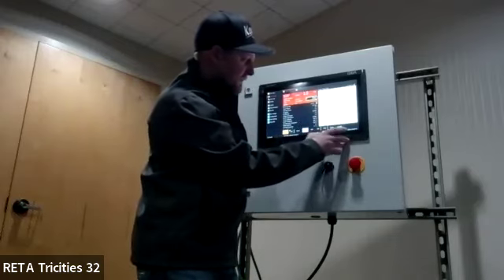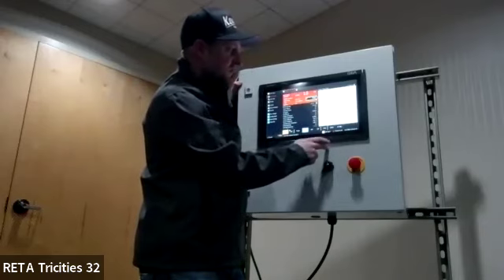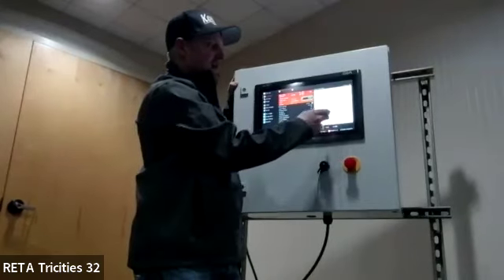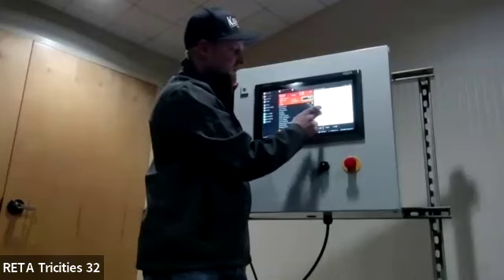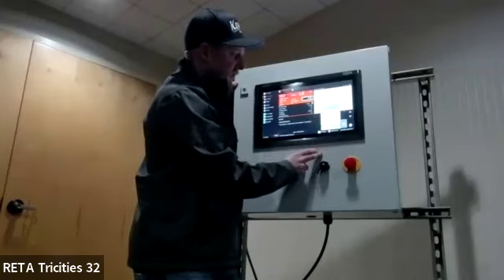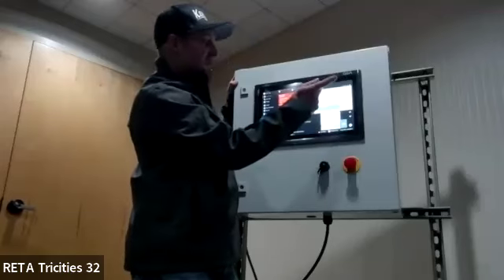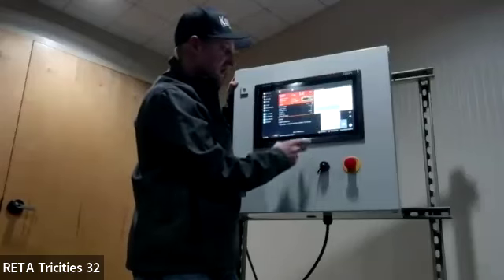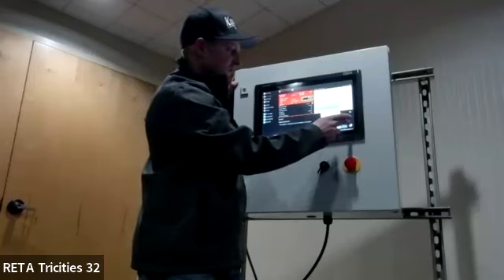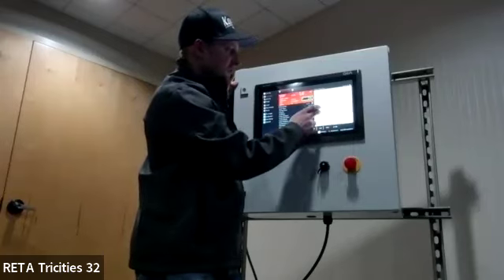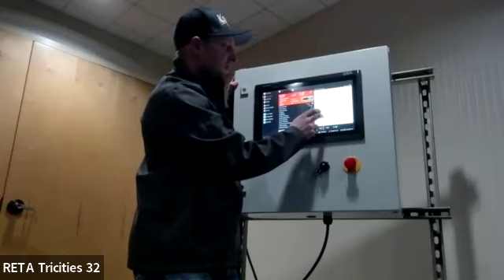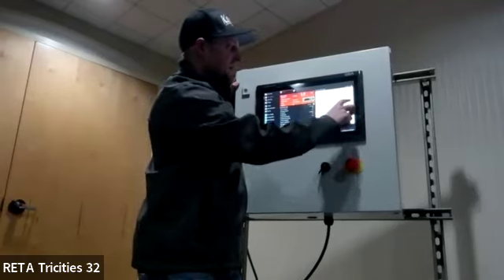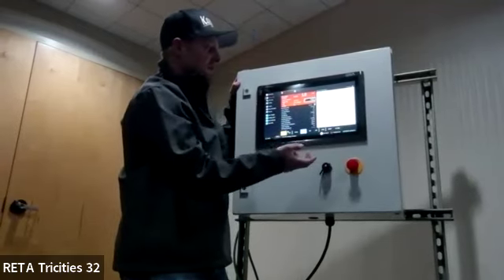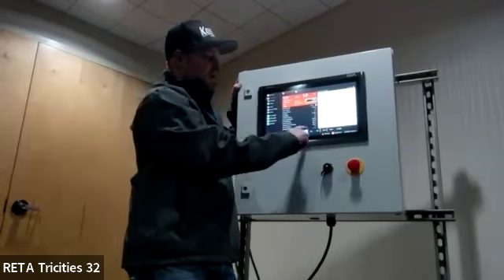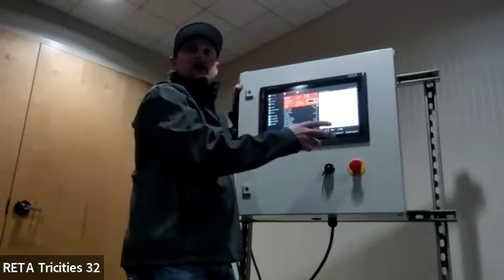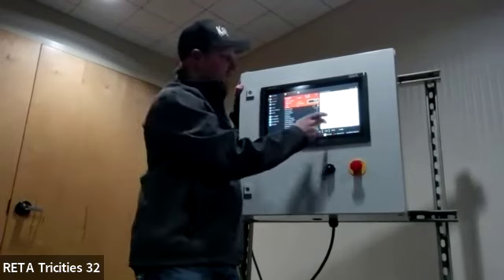So here's where you can do stopping and starting sequences. You can unload slide valve and variable speed drive in parallel. This is set up for a VFD. That's what it's going to do. Other option is you can stop compressor immediately. You can unload variable speed drive and slide in series. There's several different options you can choose from there. This is, like I said, set up for a variable VI right now. You can set the VI deadband. You can set the VI operating mode to manual. So if you wanted to see it come down here, you can actually manually load and unload the VI.